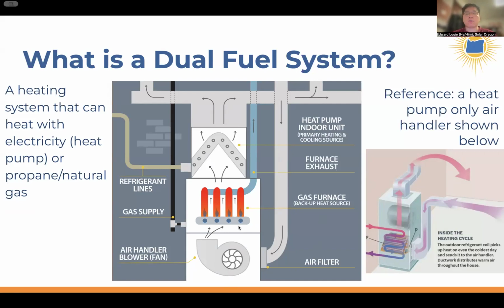That's not the same compared to a heat pump, where you need electricity to not only run the fan and the thermostat and the control board, but you also need to run that compressor and the relatively large fan outside on the outdoor unit in order to power all those components during a power outage. So you would need a smaller generator to power a gas furnace during a power outage compared to powering a heat pump, or the generator would need to work less hard and therefore can run for more hours powering a gas furnace during a power outage compared to a heat pump.